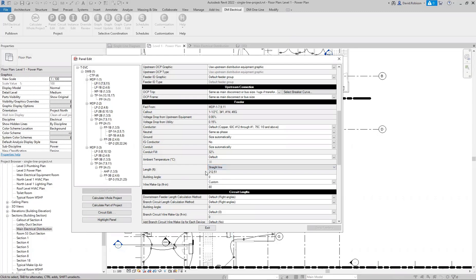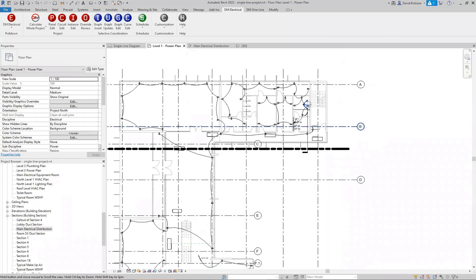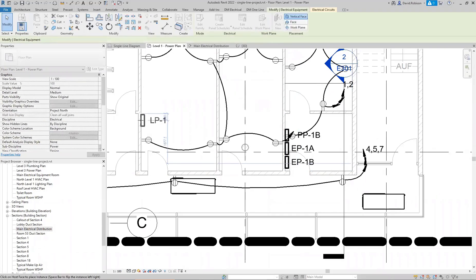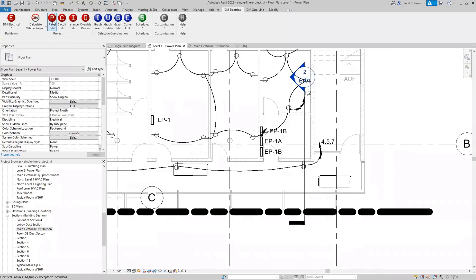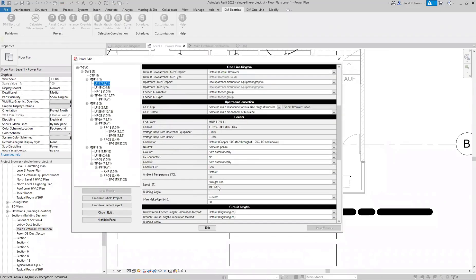For the calculated lengths, they are pulled from the project. So with straight line, if we move a panel in the project, it adjusts the length automatically. Moving the panel changed the length from 212 to 198 feet. These lengths drive the fault calculation, voltage drop, and arc flash calculations in Design Master Electrical.